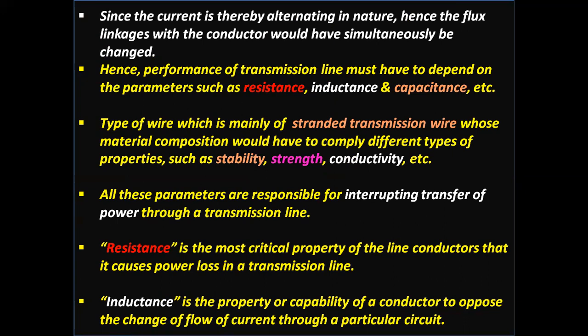The type of wire, which is mainly stranded transmission wire, has a material composition that must comply with different properties such as stability, strength, conductivity, etc. All these parameters are responsible for interrupting the transfer of power through a transmission line. Resistance is the most critical property of the line conductors, as it causes power loss in a transmission line, that is, I square R loss.